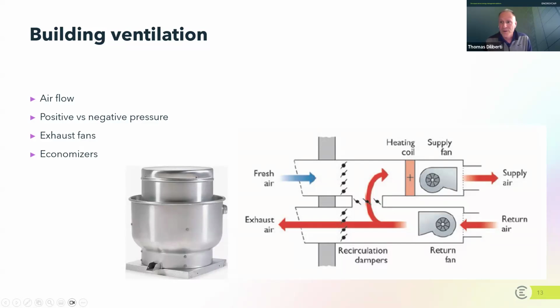So if you can imagine the air flowing into a building, eventually that air has to come out of the building. That return air, sometimes it is pulled, sometimes it is pushed, but the air comes back. And before exiting a building, sometimes there are these recirculation dampers. They are like little blinds, if you will, like mini blinds at home where you can open and close them. These dampers function in much the same way. So the air coming from the space can be ejected from the building and become exhaust air. Or if these dampers change position, they can redirect that air back into the building, because maybe the air was already fresh and you had to heat or cool it. It was in the building and now it's coming back around and you simply don't want to give it away. You want to keep it in order to keep the building comfortable. So this flow of air is very common.